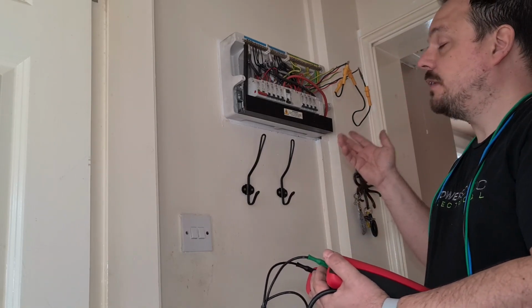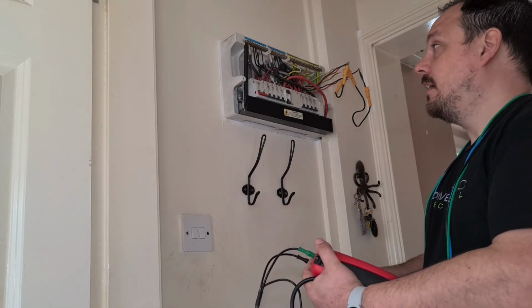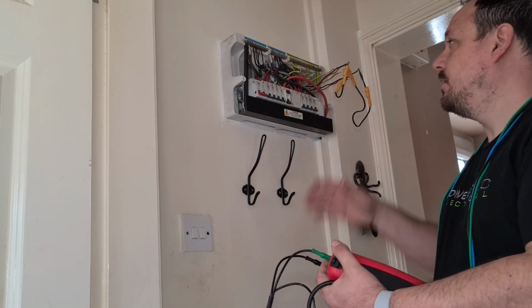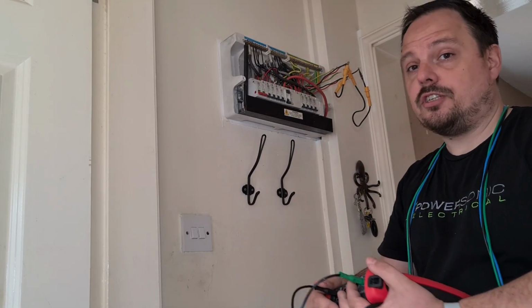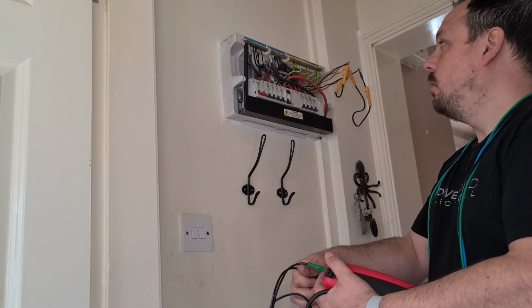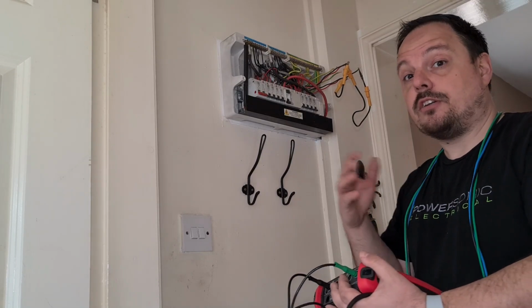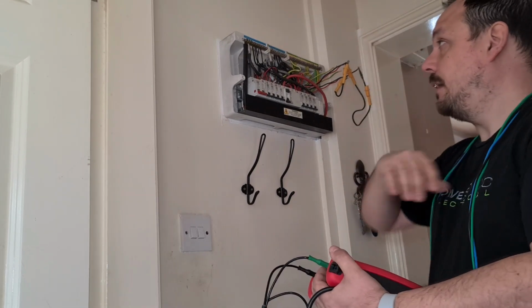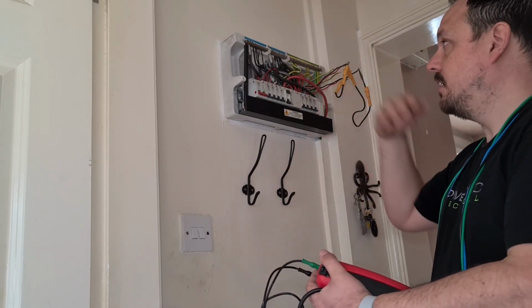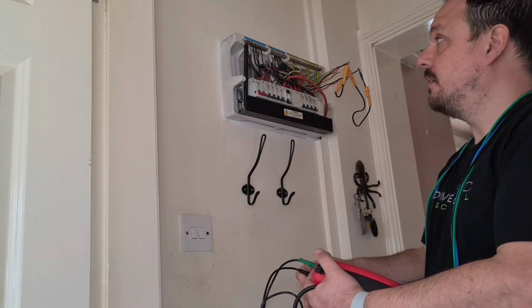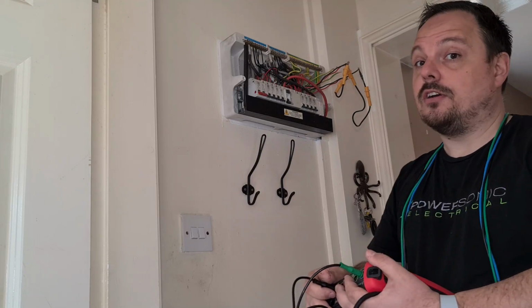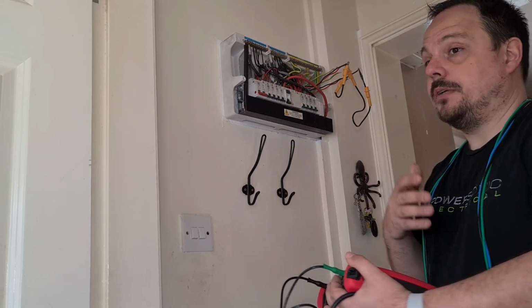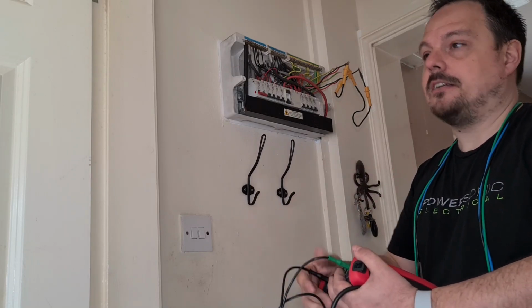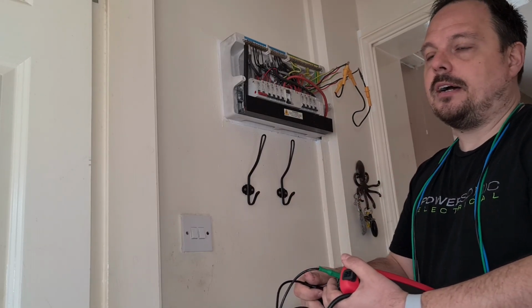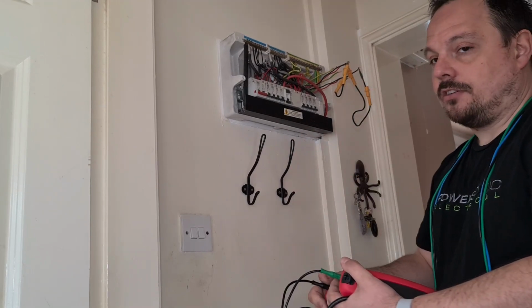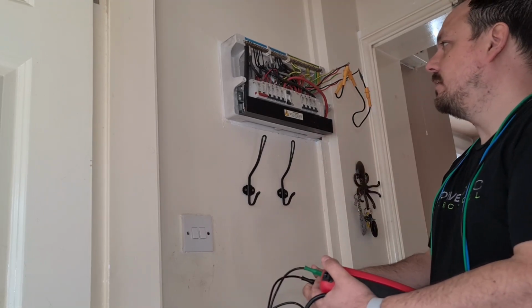And then yeah, you're at the stage where you do an insulation resistance test. Now you can do the global IR, which in that case you basically dress all of the cables back into the consumer unit. You must make sure everything is connected when you're doing your IR testing. So obviously when you're doing your continuity testing, you don't want any of those parallel paths in place on the circuit, so you've got them disconnected from the earthing system. But when you're doing your insulation resistance testing, it's very important that all of those are in place, because you could be having a leak through some of the cabling into the bonding, for example, or some other part of the building that would find its way back to the consumer unit. So you must make sure everything is dressed away.